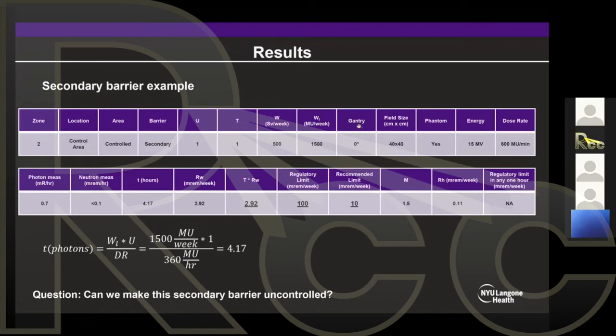Then we're going to have the gantry at 0 for this measurement, but this will be repeated for any cardinal angle. We're going to have the field size 40 by 40. We're going to have a phantom in the beam. And again, we're going to use very worst conditions, a higher energy, higher dose rate.